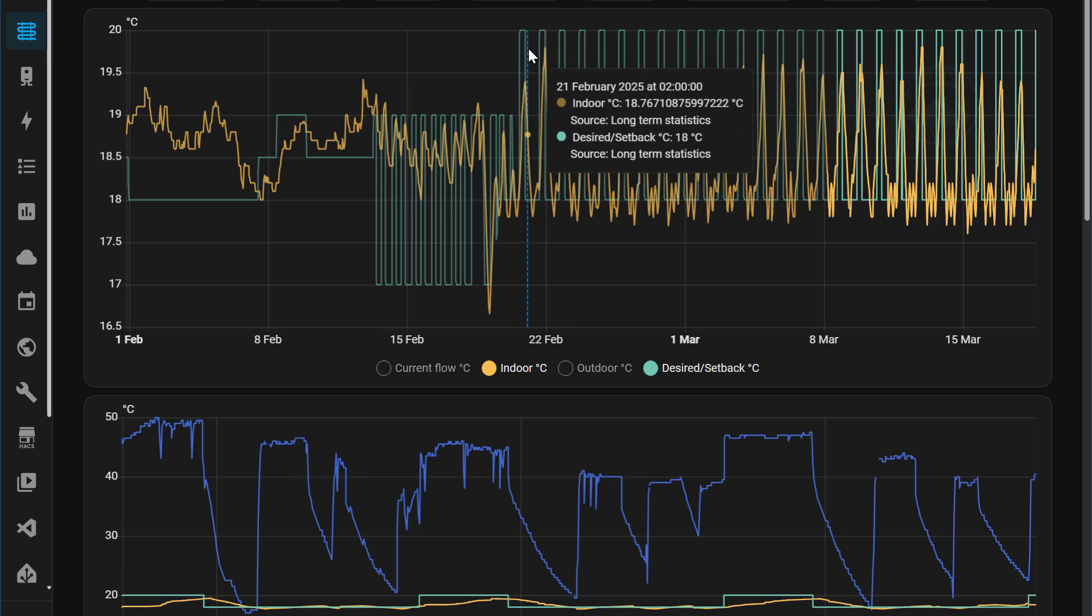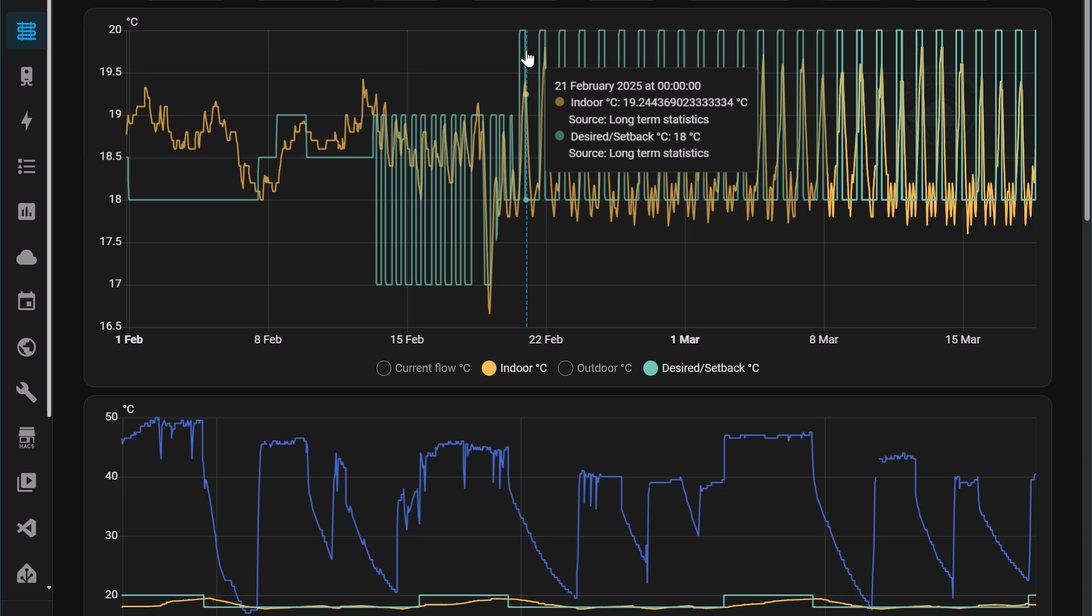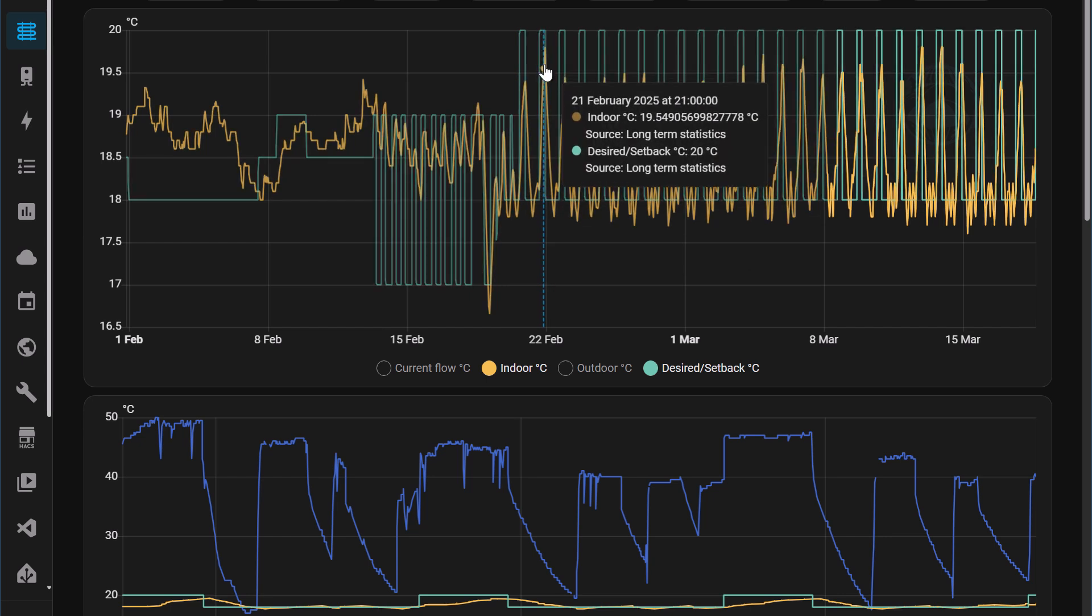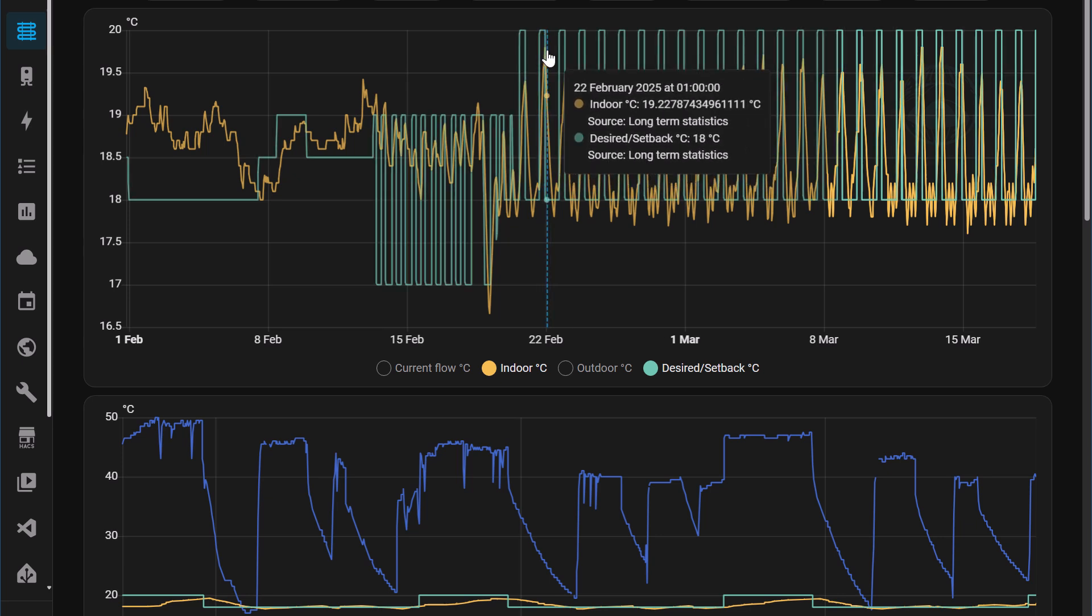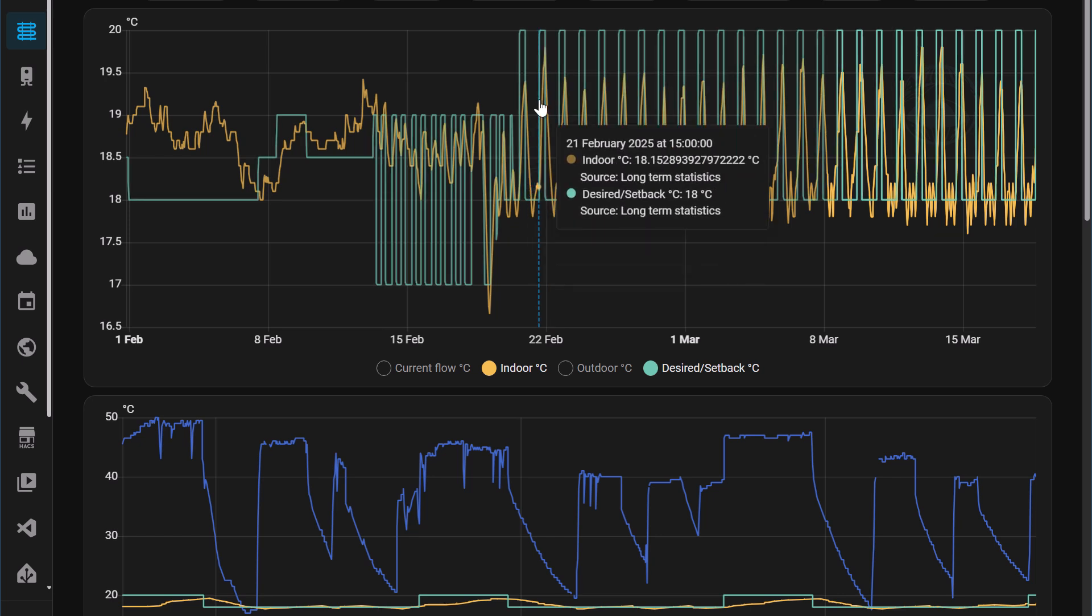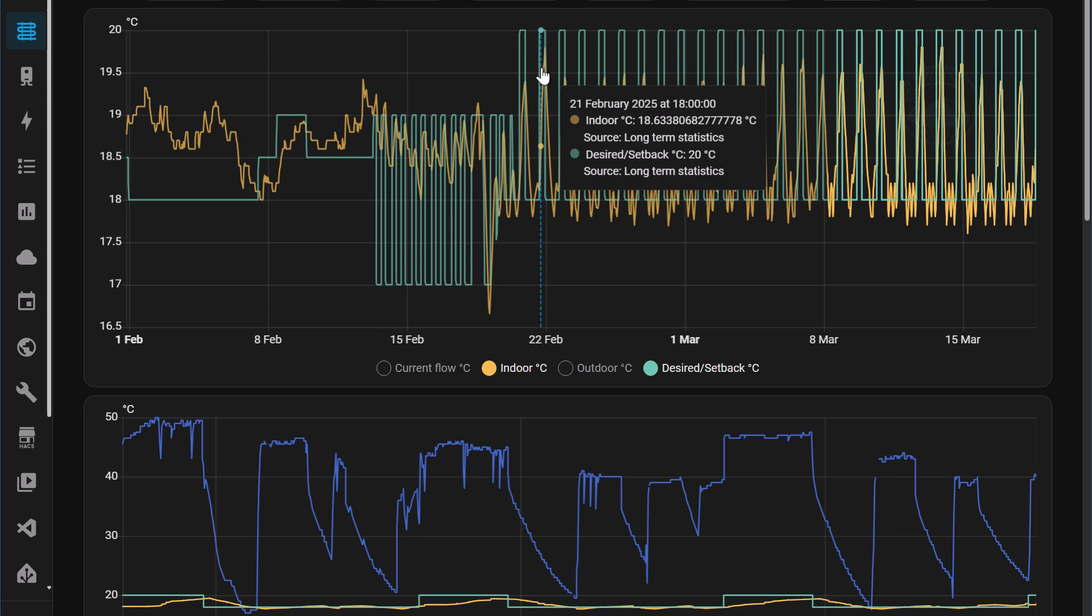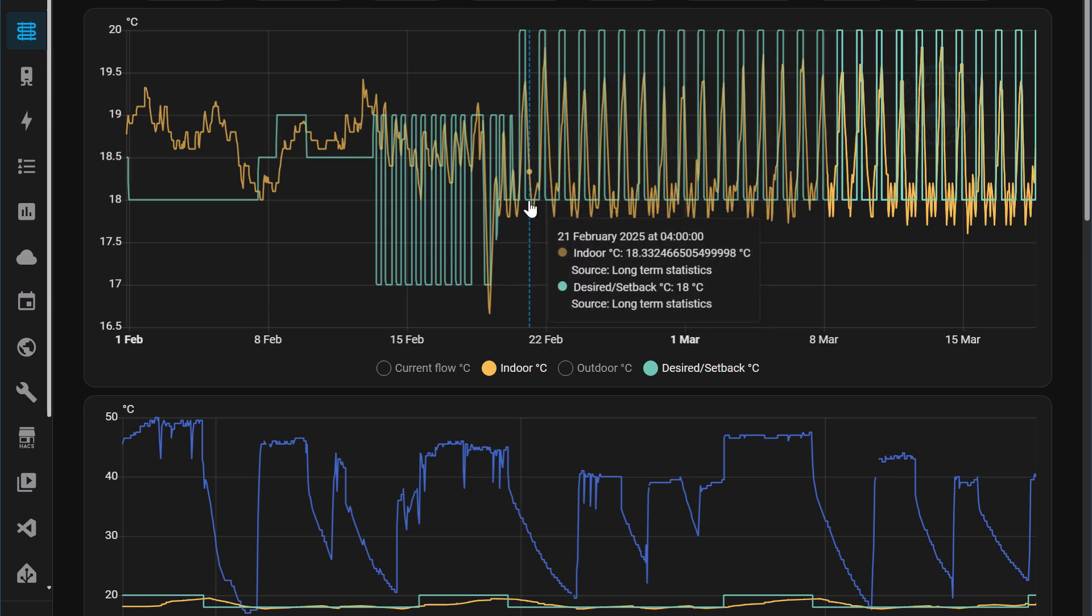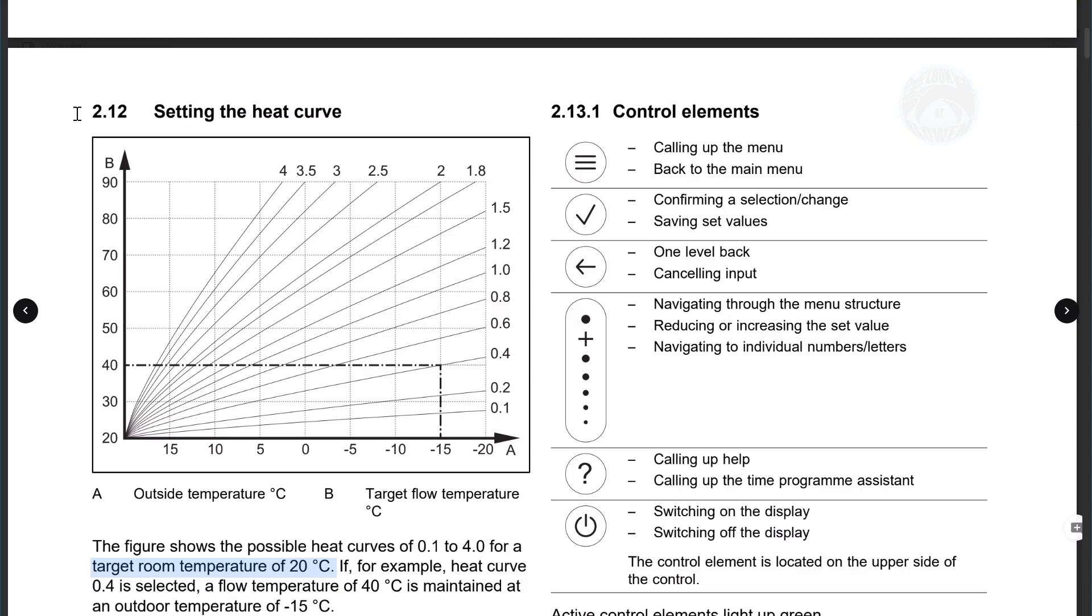What I did was I set a window starting at four o'clock and it would end at eleven o'clock. And as you can see in all of these examples right here, it never reaches the desired temperature, which is absolutely perfect because A, I'm only wanting the temperature to go to about 19.5 and B, it's long enough in that little timer to actually reach that desired temperature of 19.5 or 19 that I'm wanting. And the third thing that makes this a lot more interesting is that the fact that I've set the desired temperature to 20 degrees and the setback temperature to 18 degrees. And that is because I'm now matching the heat curve example in the manual.